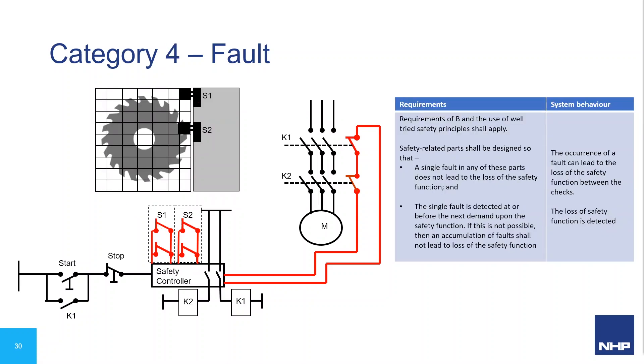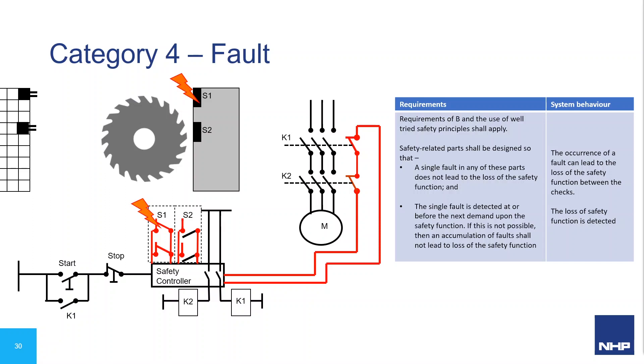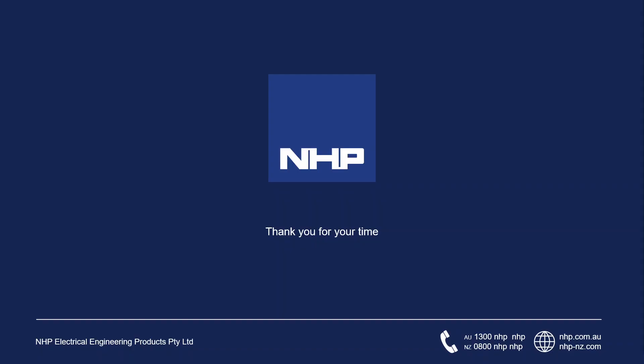In Category 4, S1 and S2 are wired into the safety controller using separate input pairs. With the same fault on S1, the motor still de-energizes — a single fault does not lead to loss of safety — and now the controller detects that both switches did not open simultaneously. It is detected on the demand of the safety function, and the system prevents restart until the fault is corrected. By now you should have a better understanding of safety control systems, safety categories, and performance levels. This was Part 1 of Safety Essentials — in Part 2 we'll look at safety products available from NHP and examples of their application.